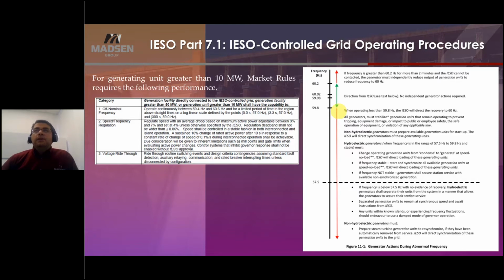And IESO has been implementing these and going to the plants, and I've personally worked with one of them, so that we go to the plant and we do some testing to make sure that we are maintaining the frequency. Or if you are using one of your turbines with droop control, IESO wants to make sure that if for any reason there was a change in the frequency, how quickly your governor will recover and what error comes out of that.